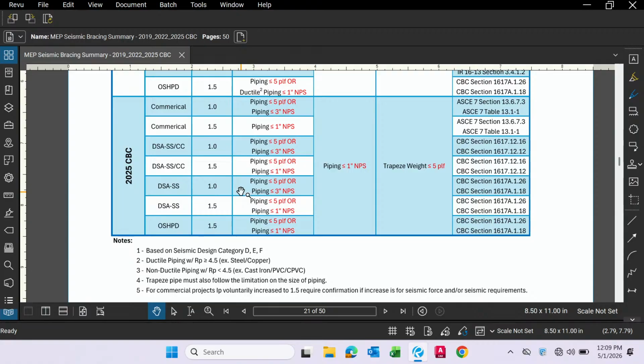And then if it's a commercial project where the importance factor is 1.5, right? So for example, say it's a risk category 4 building. You have to brace everything down to 1 inch. See? So the only exemption is 1 inch or less now if it's an importance factor of 1.5. So you can see the big jump there as far as bracing requirements. Okay? 1 inch or less with an importance factor of 1.5 can be exempted. Right. Any questions so far?